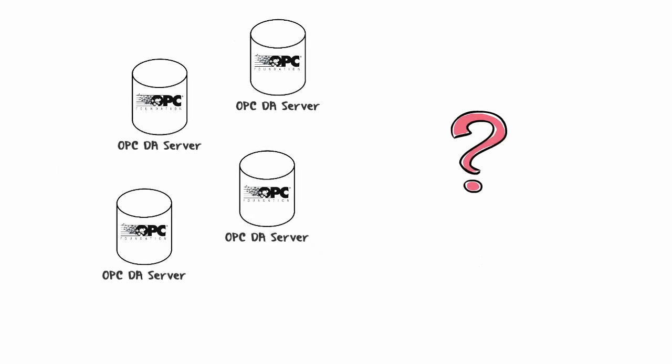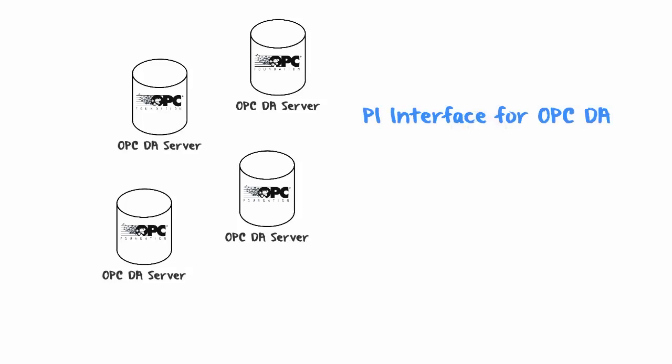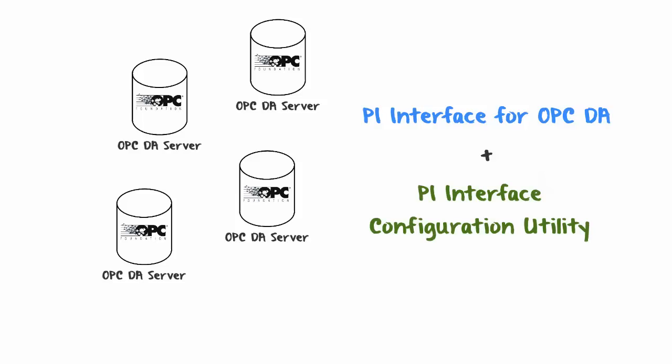If you have multiple OPC DA servers, you do not need to install the PI Interface for OPC DA multiple times. All you need is a single PI Interface for OPC DA installation, and you configure multiple instances of it. To do that you need the PI Interface Configuration Utility. And even if you only have a single OPC DA server, you will still need the PI Interface Configuration Utility, since this is the GUI used to create, configure, and maintain instances of the PI Interface for OPC DA. You will need to install both of these components.